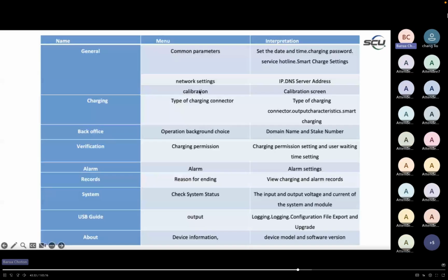So let me go back to this table - as you can see, these are all the different functionalities we have. In the general tab, we can set the date and time, change passwords, put a phone number for service, and configure smart charge settings. Smart charge settings let you set limitations if you want to control the power - so let's say you bought a 240 kilowatt charger, you can make it 180, 150, or any power you want, you can limit the power. That's all under the general tab. In network settings, it's like the server settings. And if you replace the display and need to do a calibration, you can calibrate the screen from the general tab as well.